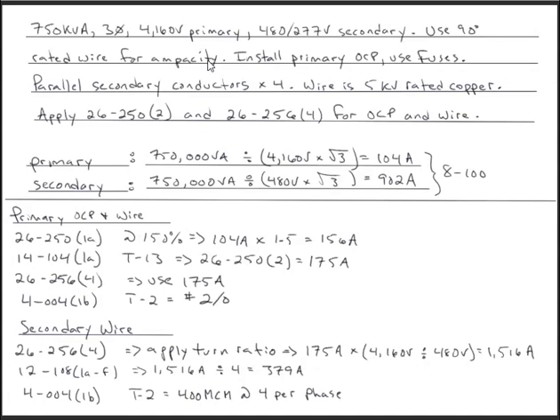the codebook pretty much rules the roost. The codebook always assumes that the equipment is not marked. That will always give us the higher standard. So I just chose 90 degrees, that the equipment is marked for 90 degrees, just to give the lesson a little flavor instead of always having equipment not marked. So this is just playing with the numbers a little bit in the code book for the sake of changing things up. Always refer to the manufacturer and find out what the equipment is marked for.